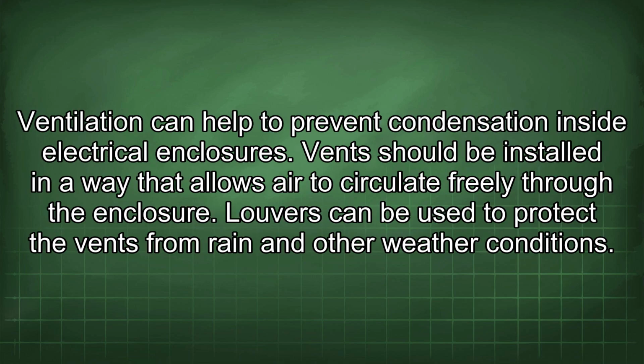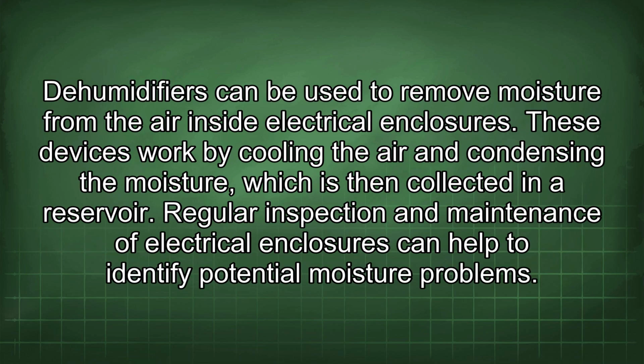Ventilation can help to prevent condensation inside electrical enclosures. Vents should be installed in a way that allows air to circulate freely through the enclosure. Louvers can be used to protect the vents from rain and other weather conditions. Dehumidifiers can be used to remove moisture from the air inside electrical enclosures. These devices work by cooling the air and condensing the moisture, which is then collected in a reservoir.